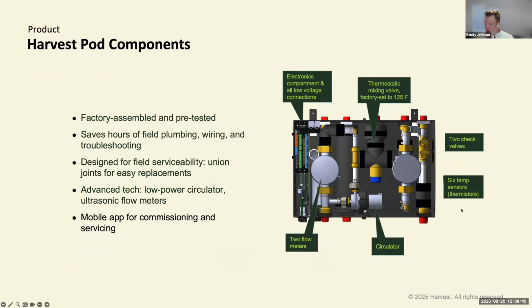I think I got most of that, Tyler - I may ask you to clarify the tail end. The short answer is the mixing valve is in the pod, right in the middle there. It's adjustable, factory set at 125 degrees. The reason we need that in the pod is because we're making water at about 150 degrees, which is way too hot for domestic water, but much better and denser for the space heating application. That's why it's built in there.